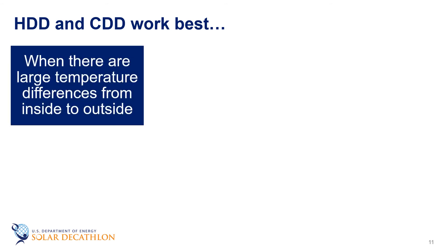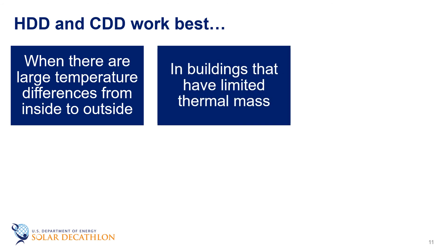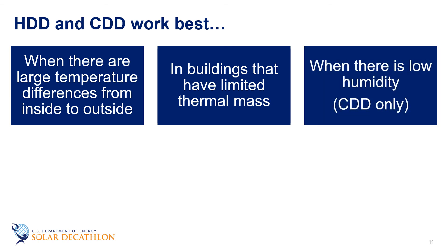Heating and cooling degree days tend to work best when there are large temperature differences from inside to outside and in buildings that have limited thermal mass which acts to store heat. In addition, on the cooling side, if there's a lot of humidity, cooling degree days tend to be less accurate.